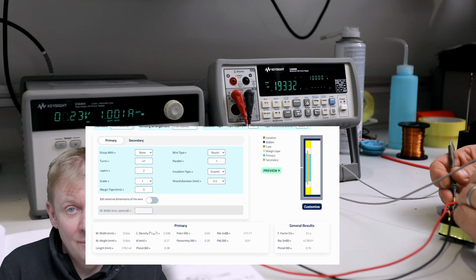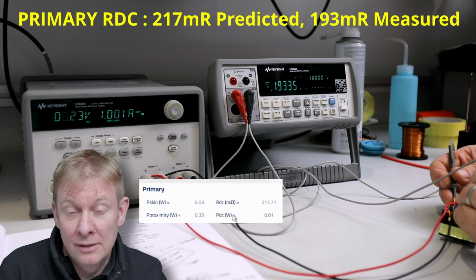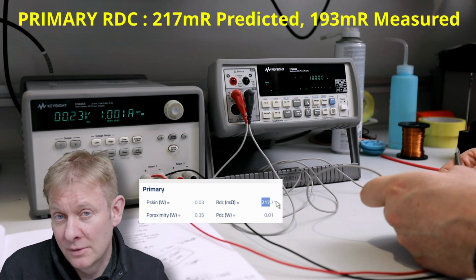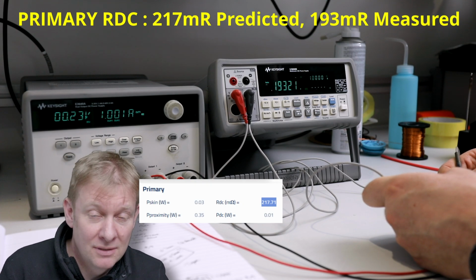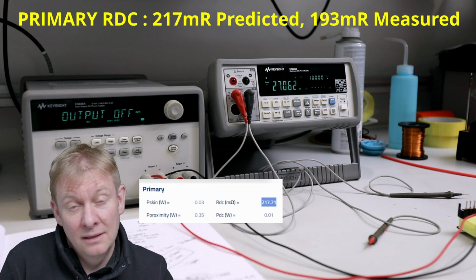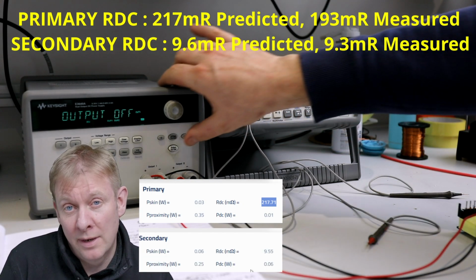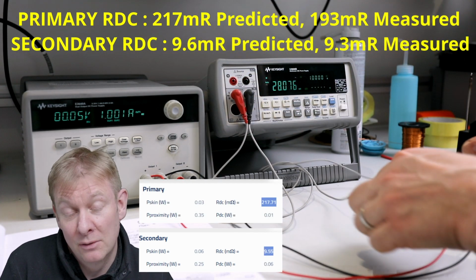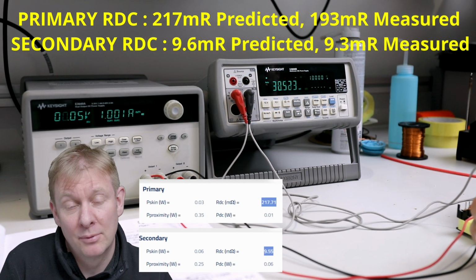And in the case of the primary, 1 amp DC current flowing drops around about 190 millivolts, so that gives us 190 milliohms DC resistance. And in the case of the secondary, that same 1 amp causes a 9.3 millivolt drop across the winding, so about 9.3 milliohms.